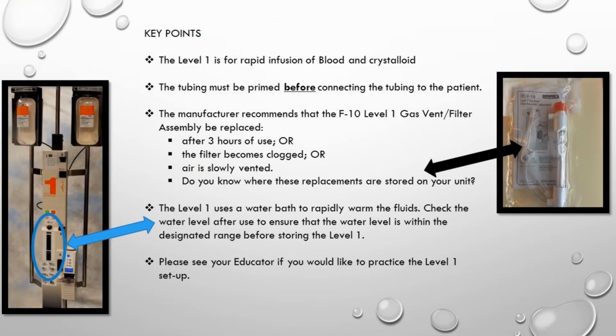To summarize, here are some level 1 infuser key points. The level 1 is for rapid infusion of blood and crystalloid products only. The tubing must be primed before connecting the tubing to the patient. The manufacturer recommends that the gas vent filter, which you see pictured on your right, should be replaced after 3 hours of use, or the filter becomes clogged, or air is slowly being vented.